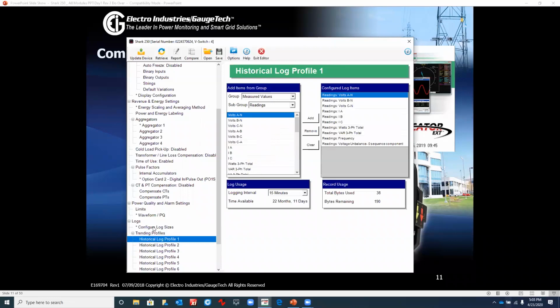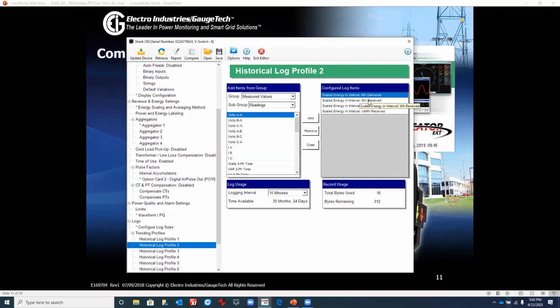So log 2 is set up for energy, and this is a typical log that most people use to retrieve meter data, so interval data. In this case, the meter is programmed with scaled energy in an interval: watt hours delivered, watt hours received, var hours delivered, var hours received. And that's a 4-channel configuration.